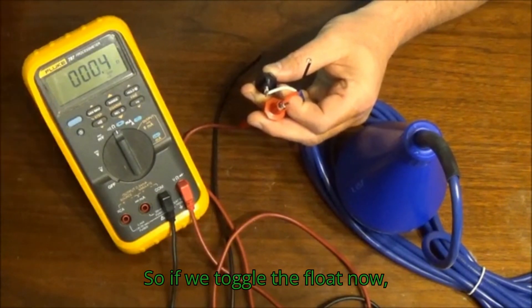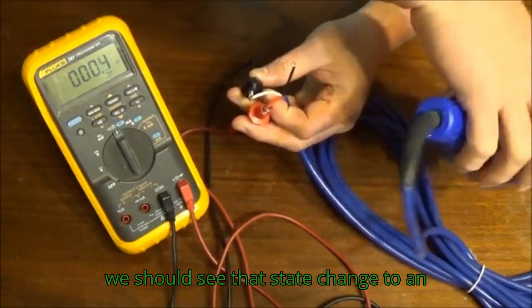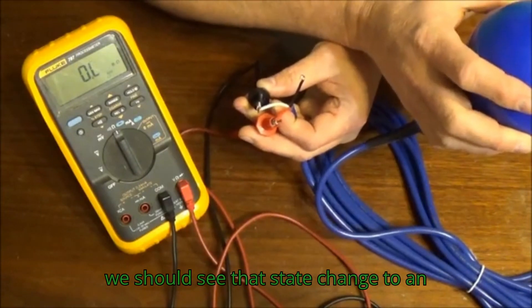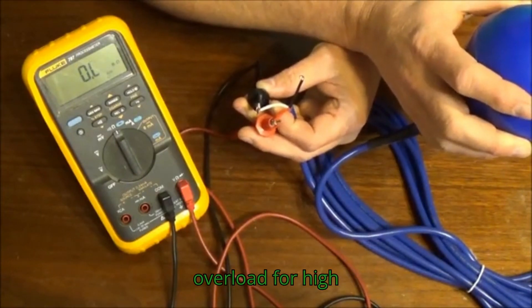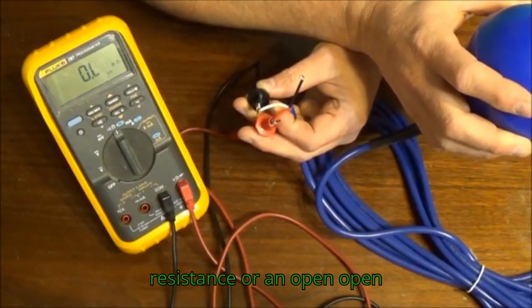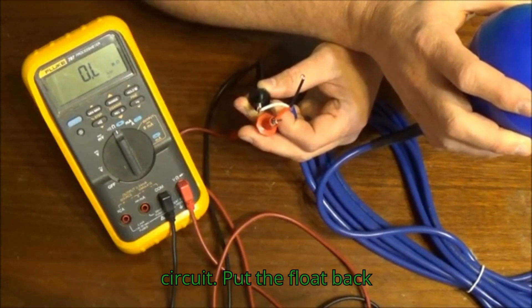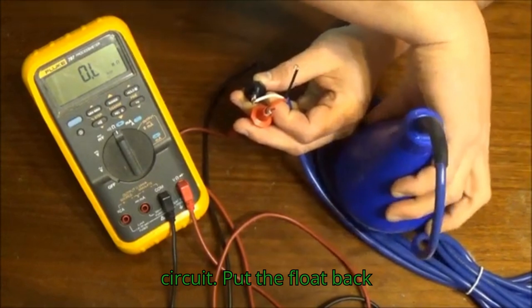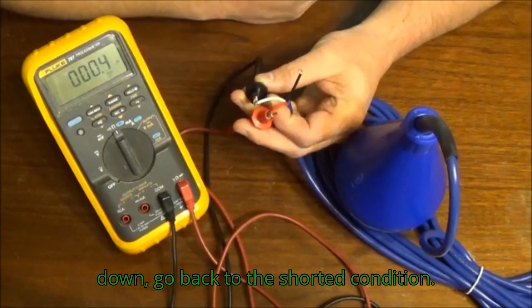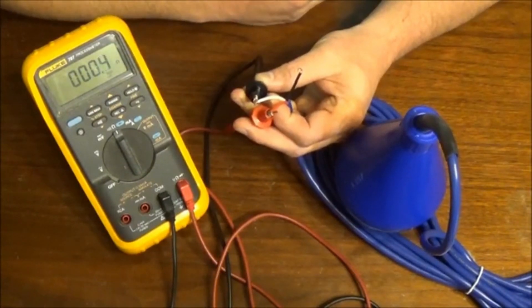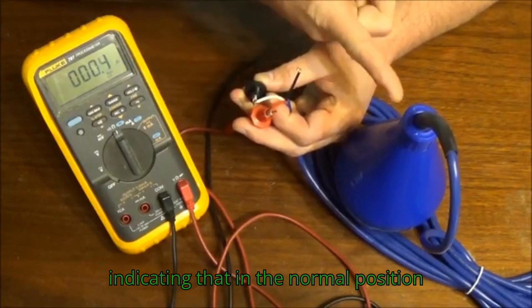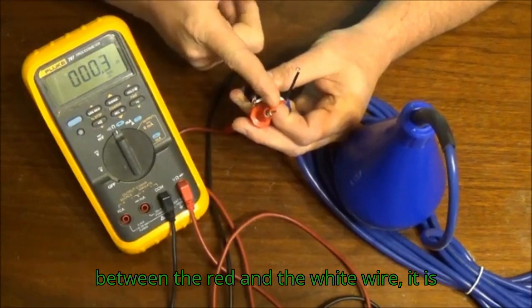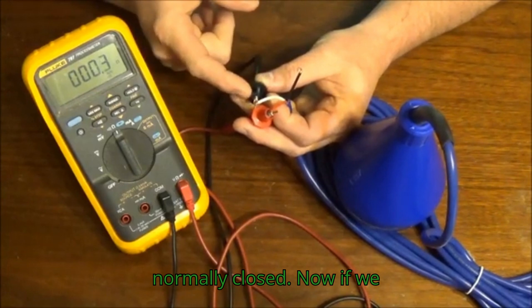If we toggle the float now, we should see that state change to an overload for high resistance or an open circuit. Put the float back down, go back to the shorted condition, indicating that in the normal position between the red and the white wire, it is normally closed.